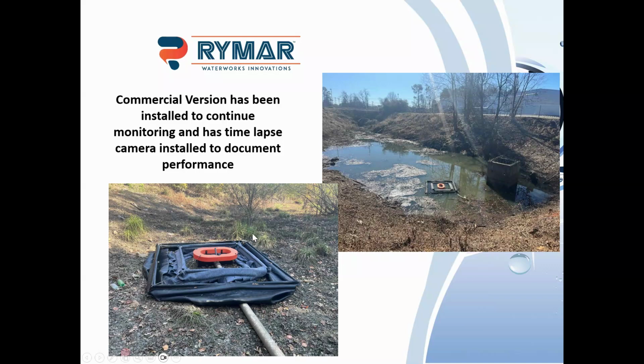We've got a time-lapse camera set up here to monitor it, so we can keep an eye on things and make sure it's working. We're going to monitor this for the next several years. We'll just keep this filter in there to see exactly how long it lasts. We're predicting a minimum of 2 years, which is what our maintenance schedule is right now. But we'll see how much longer it lasts and how effective it is through the seasons.